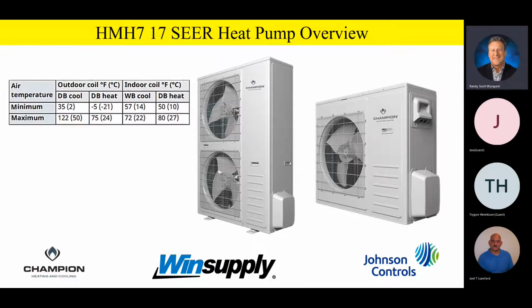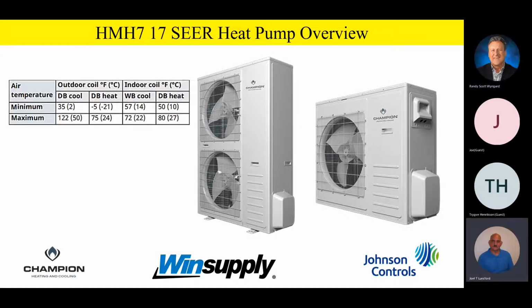Joel, I have one here. Sure. At -5 in heating, does the unit continue to try to run, or does it lock out at -5? That's a good question. I've actually had field reports of it doing both. So basically, it'll throw a little code, and then it will go through a lockout procedure. But if you think about it, that -5 minimum temperature for heating, at that point, the heat pump has reached a point, Randy, where, and that's a good question, it reaches a point where the amount of heat that it's generating is not going to be sufficient to heat the space, and that's why they do that. Okay. Good question.